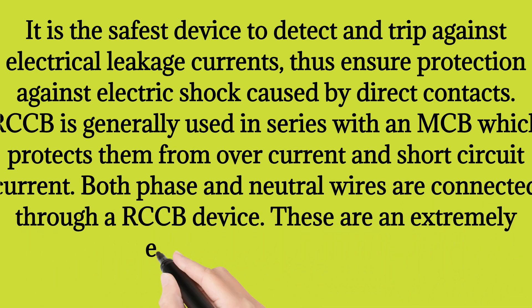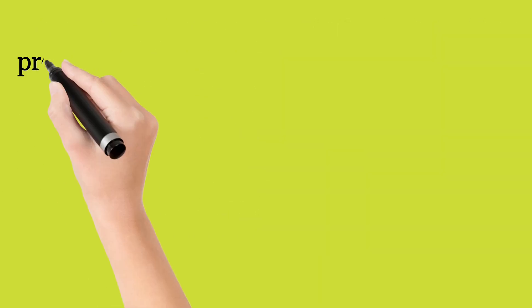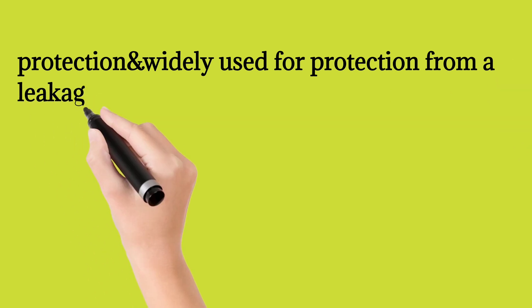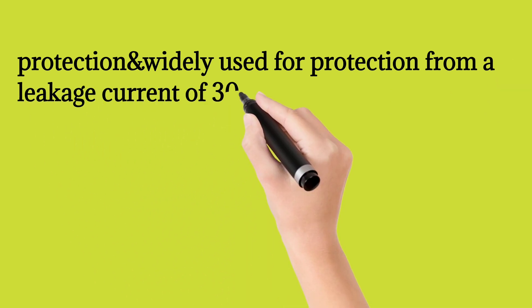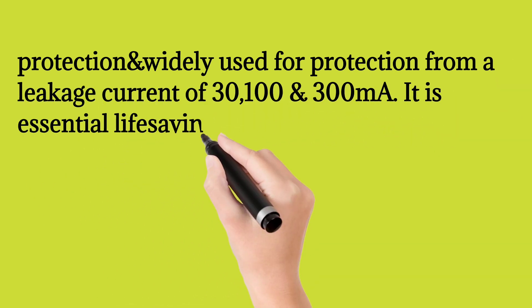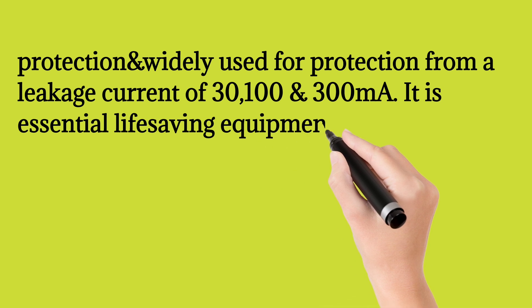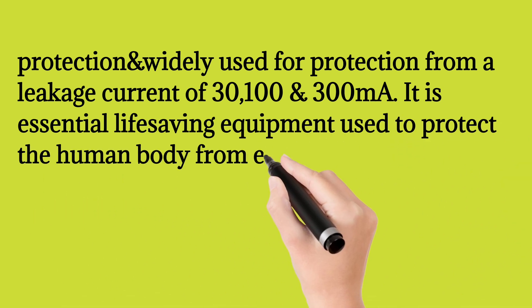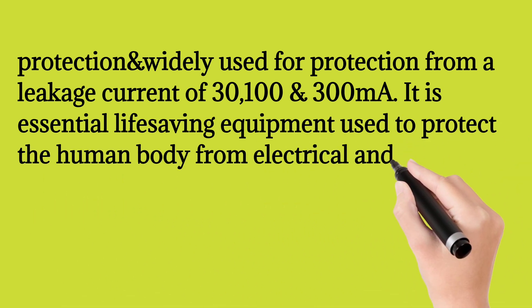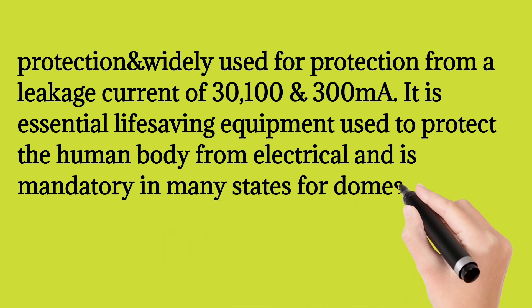RCCB is an extremely effective form of shock protection and is widely used for protection from leakage currents of 30mA, 100mA, and 300mA. It is essential life-saving equipment used to protect the human body from electrical hazards, and is mandatory in many states for domestic installation.